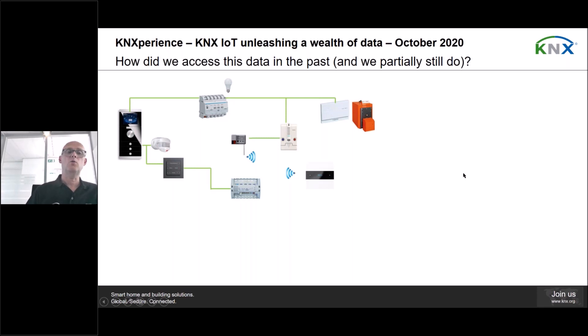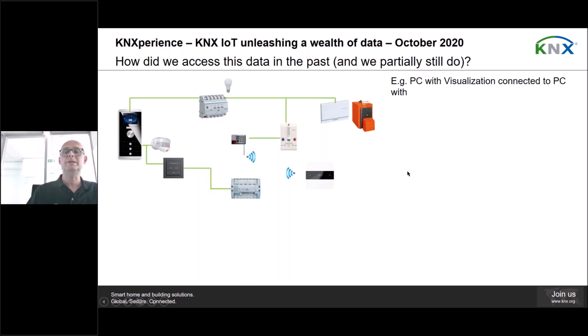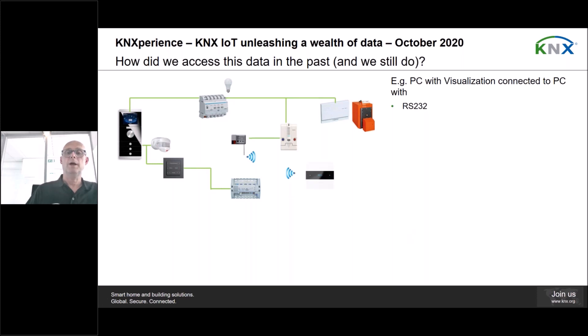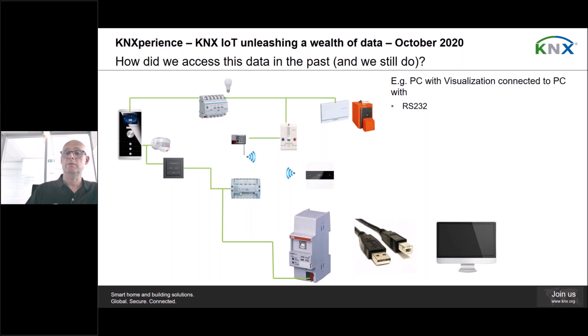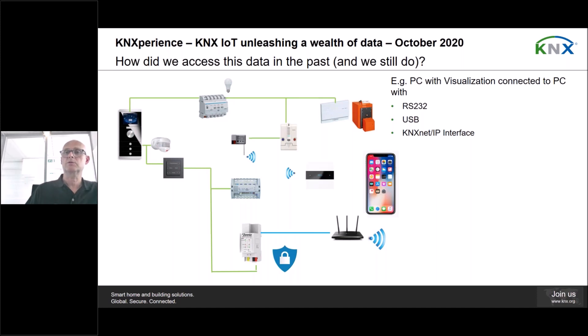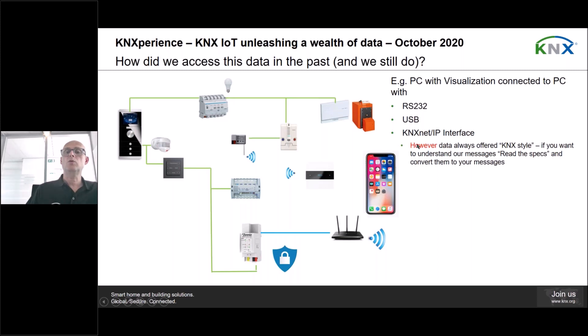Let's look at how we accessed data in the past and how we still partially do today. In the very early days, we linked a PC with visualization to the bus using RS-232. In more recent days, we could use USB. And for approximately the last 10 to 15 years, we've been able to link a KNX installation to an IP network using a KNXnet/IP interface. But for all these solutions, the data is always offered in the KNX style.